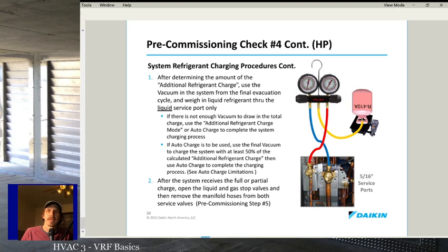Measure your line set. When it comes to charging, you have to charge mini splits and VRF systems by weight. I recommend charging every system by weight. Charging by weight is my favorite thing in the world. I charge everything by weight. I don't use subcooling or superheat to charge a system initially, ever. I may make an adjustment even after I weigh in a charge if the TXV isn't quite meeting its factory set superheat values or something like that, but that is few and far between.